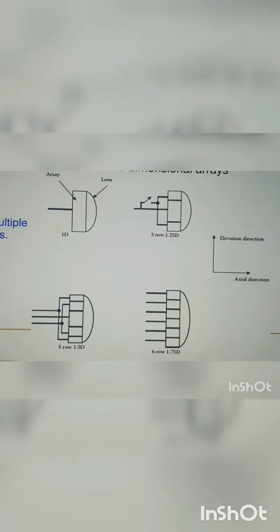What you see here are the different types of multi-dimensional arrays. The one on the top left is a 1D simple array. On the top right is a 3-row 1.25 dimensional array. The bottom left is a 5-row 1.5D array. And the bottom right is a 6-row 1.75D array. For a one-dimensional array, the elevation aperture and focal distances are fixed.